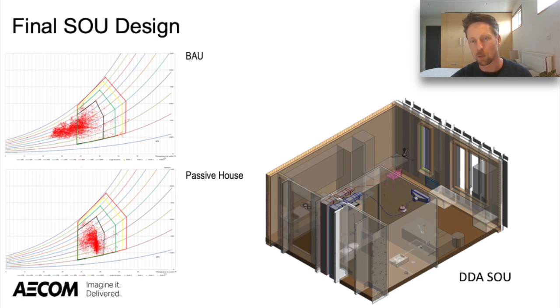For those warmer days, we envisage the space would reach upward of 30 degrees for a few hours in the year, and to ensure comfort at those temperatures, each space has a ceiling fan. Considering air velocity as a function of temperature, the analysis suggests that for the passive house design we have almost all hours within the comfort zone for occupants, which is a testament to the design. Compared to business as usual, particularly in winter, temperatures drop right down, so heating is still required there, which we don't see here.